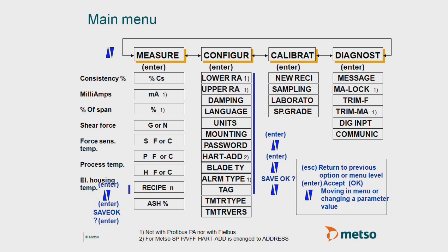Mounting is important. Mounting here helps compensate for the weight of the blade. In our scenario, we have a vertical up installation. You also have options for horizontal side mount and also horizontal top mount. But again, in our scenario, we're in the vertical up mount. The blade type is very important. In our case, we're going to select LL blade. And that's really all you have to do for configuration.